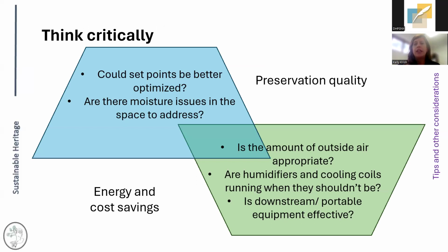And just generally, it can be really helpful in terms of thinking from both a preservation standpoint as well as a sustainability one. Dew point can be useful to see, if you have that dew point locked in, maybe there's a different combination of temperature and RH that would be appropriate for your collection and that the system could achieve, or if there are loads in the space to address.